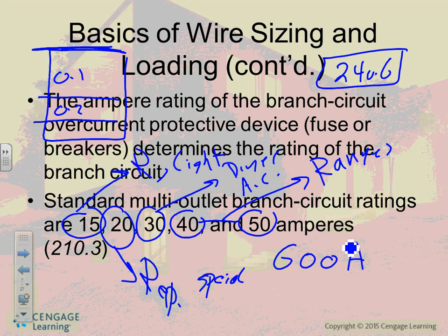Okay, gentlemen, please write yourself a note. With 15 amps, we always use gauge 14. With 20 amps, the gauge that you use, anybody? 12. Gauge 12. With 30 amps, anybody? Gauge 10. With 40 amps, anybody? Gauge 8. Write yourself a note, and gentlemen, you have just sized everything in the residential project. From the get-go. No calculation, nothing.